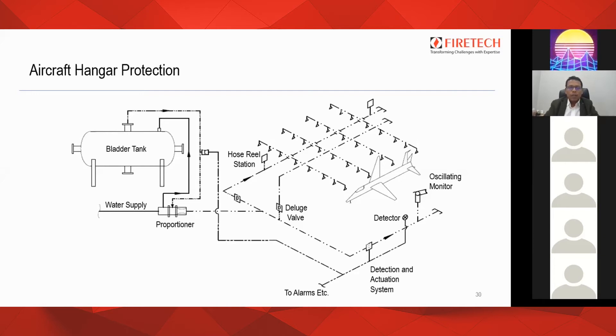The P&ID shown here is of a low expansion foam system. The basic components are the overhead sprinklers which are mounted on the top — you can see on the top of the aeroplane sketch. At the side you have the oscillating monitors to cover the area under the wingspan, which is where foam cannot be sprayed by the overhead sprinklers.